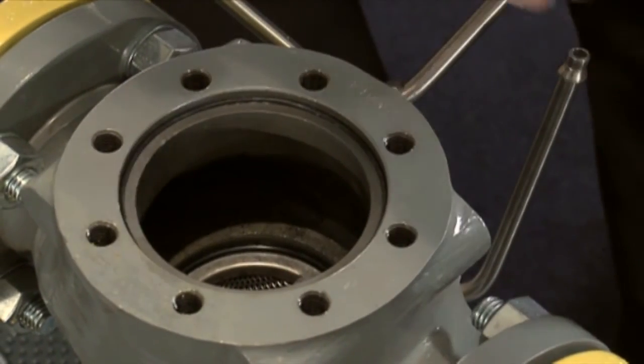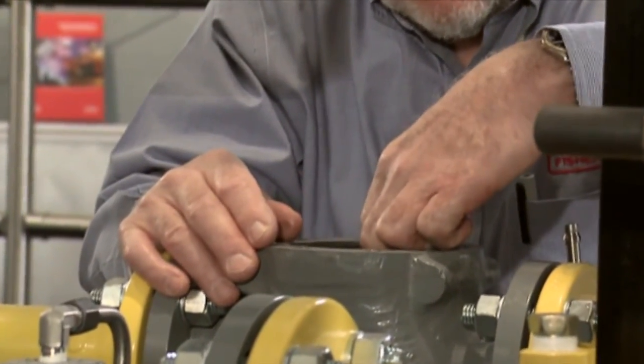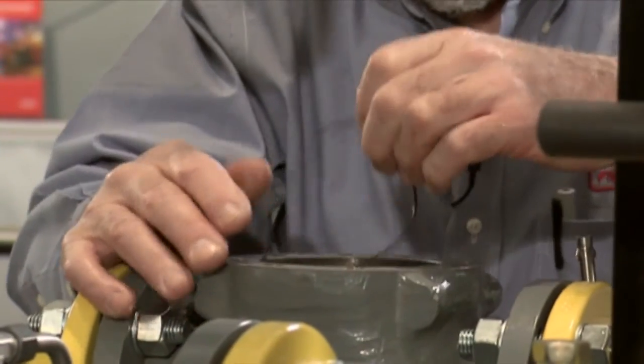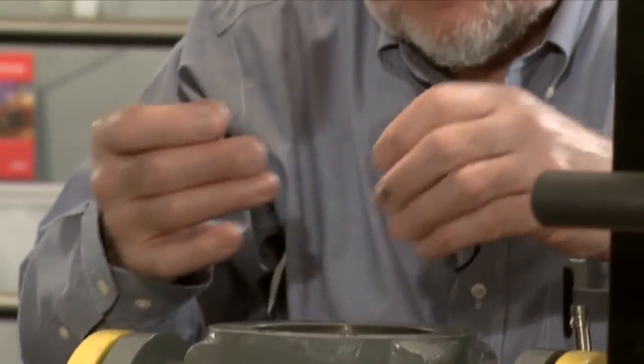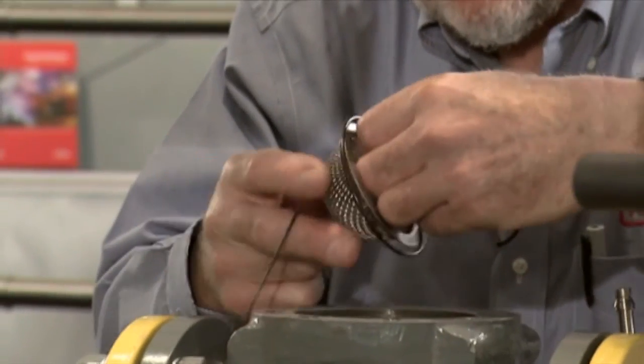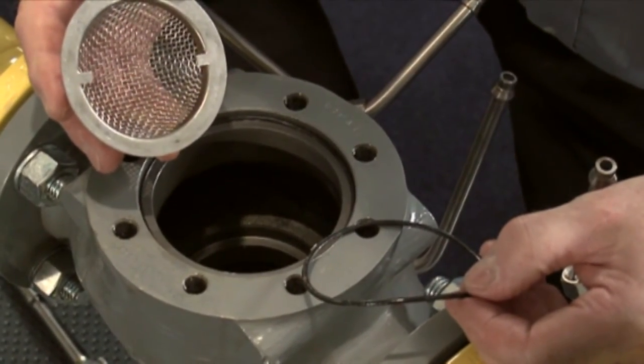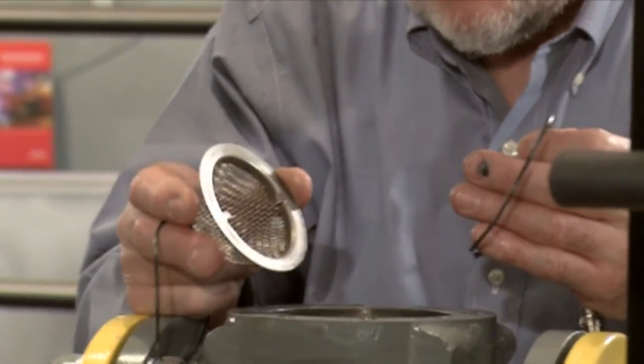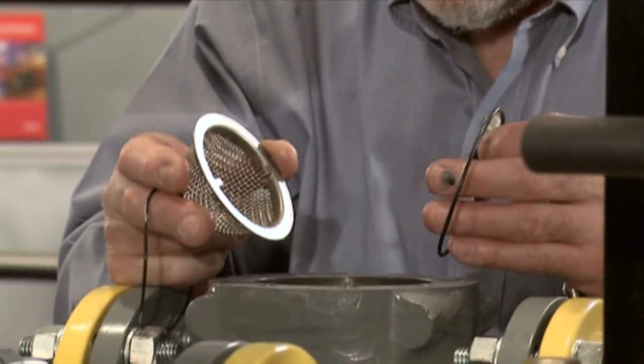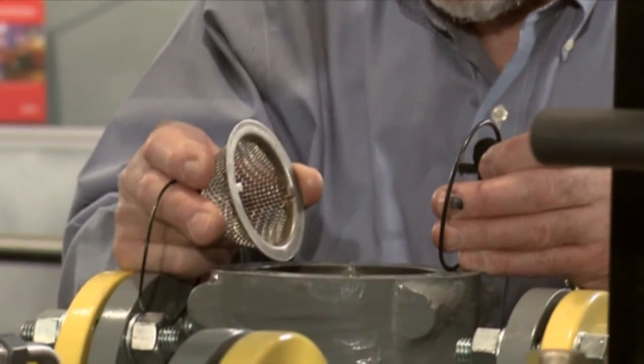We're going to remove the rest of the parts from this body. We have two o-rings in here that help us seal the unit up. First of all the bonnet o-ring, and down in the body we have a lower o-ring, and then the strainer basket. This strainer basket's purpose is to catch large particles coming through the flow stream, maybe like weld slag or something of that nature.